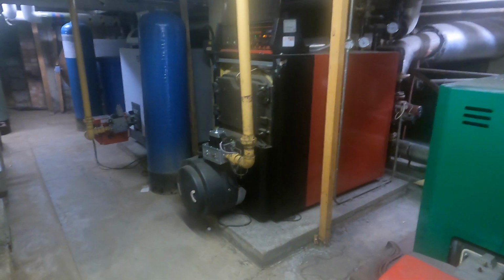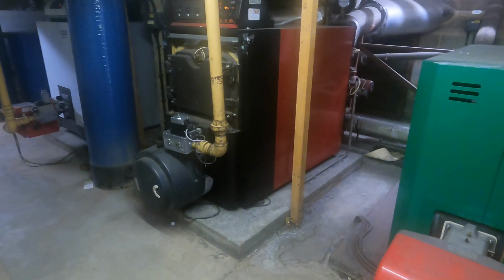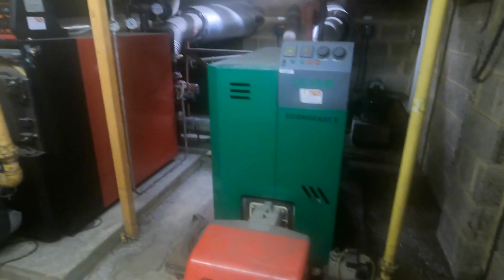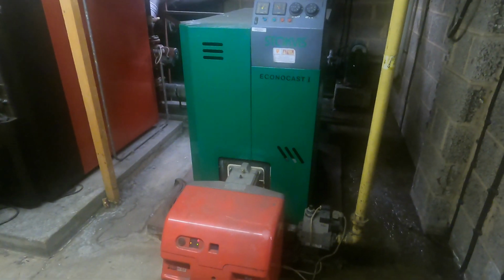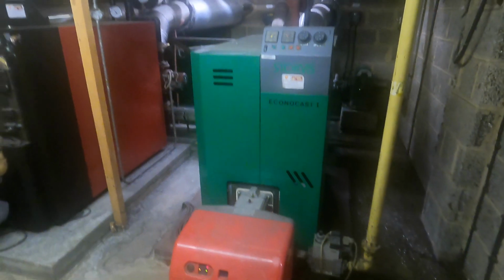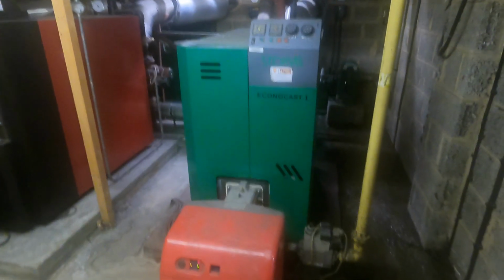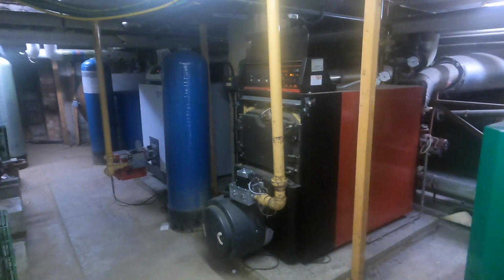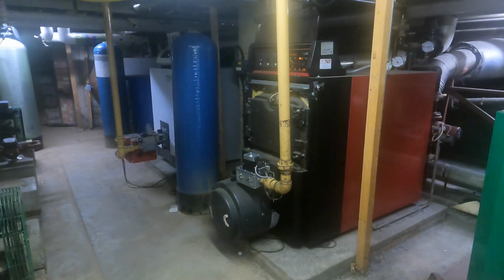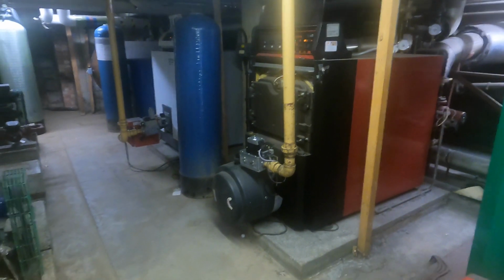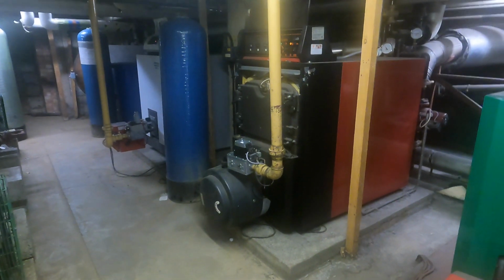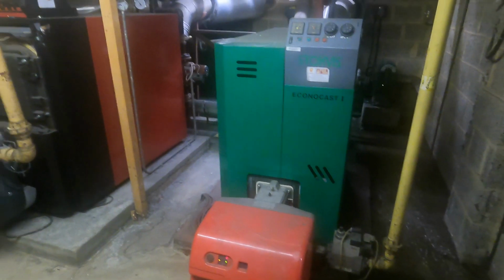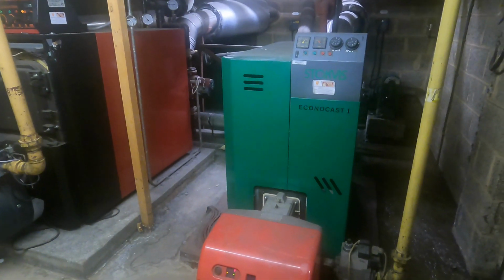The next question I want to raise here as well is we have 3 boilers. So we have 2 boilers that are similar, and then we have a smaller boiler which would be classed as our summer boiler. Now in the winter I would expect this boiler to be shut down and then just running on these 2 boilers. These 2 boilers possibly could maintain the building temperature, and then you would use this 3rd boiler just for the summer when we're only using the hot water.